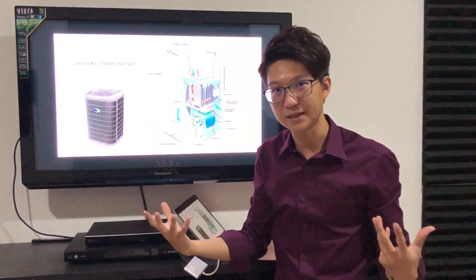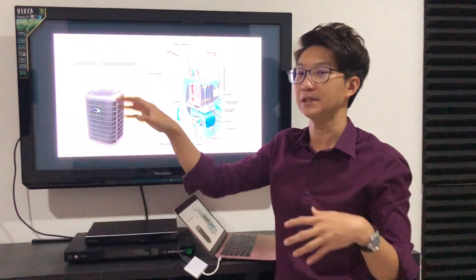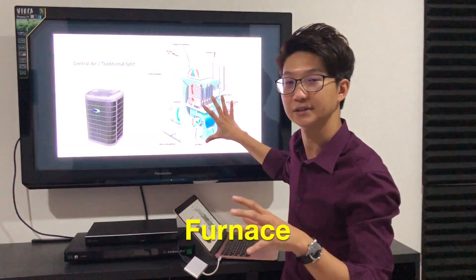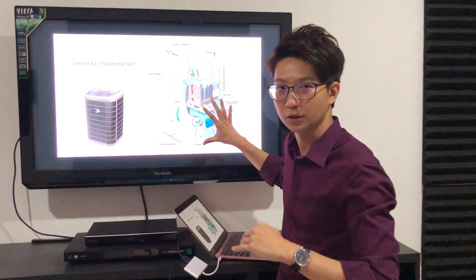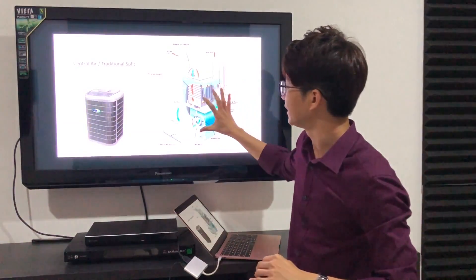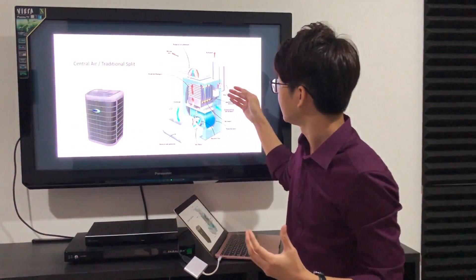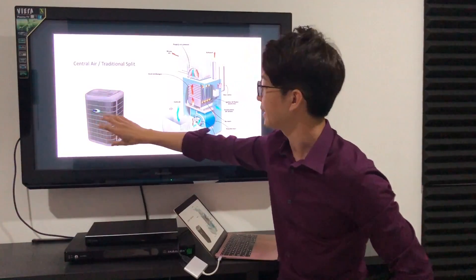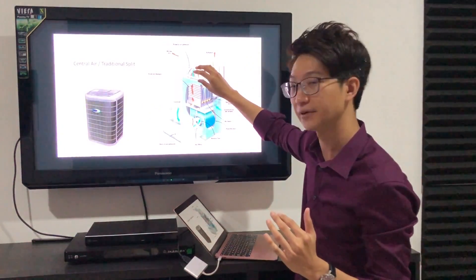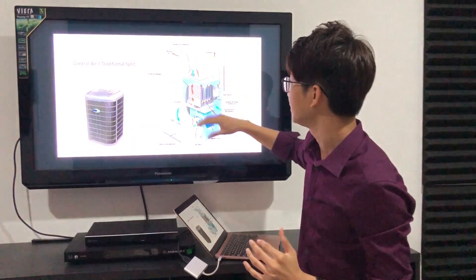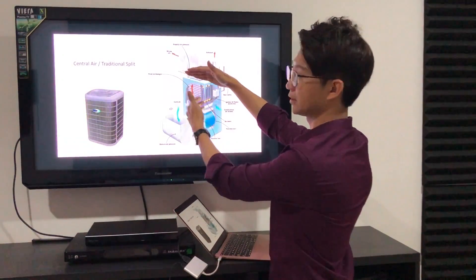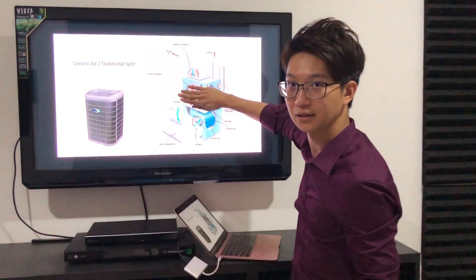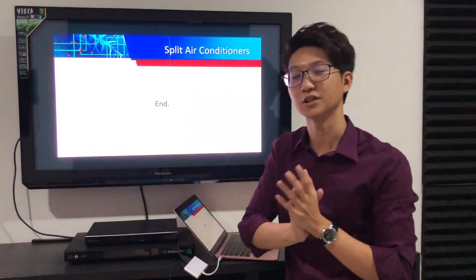Lastly, another type of split air conditioner is the traditional split, mostly used in the United States — they call it central air. This system requires a furnace because previously heat pumps couldn't work at very cold temperatures, so they needed to burn natural gas or propane. The furnace is the base system; when you need cooling, you install and hook up just an evaporator coil above it. During heating mode, you use the furnace for heat. When you need cooling, the furnace stops and the evaporator coil acts like a normal air handler. That's how the two systems are combined. That's all for split air conditioners.